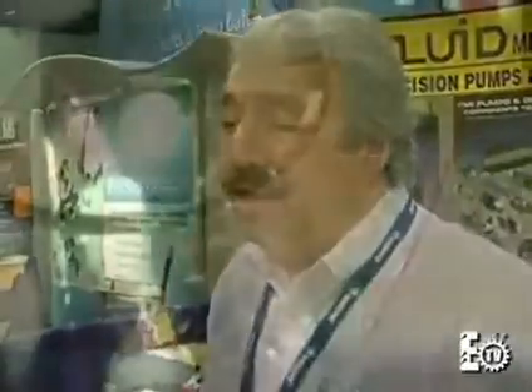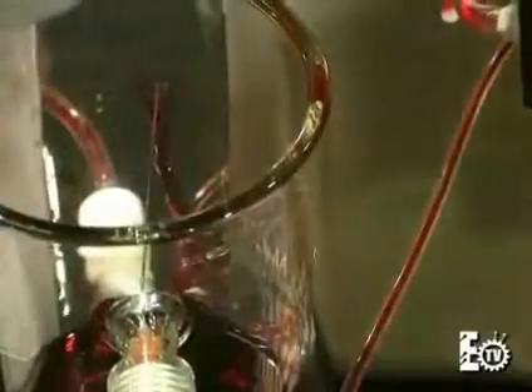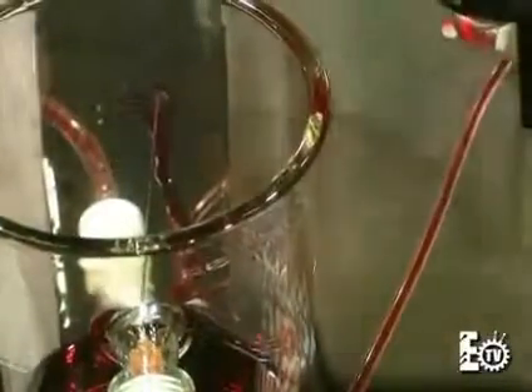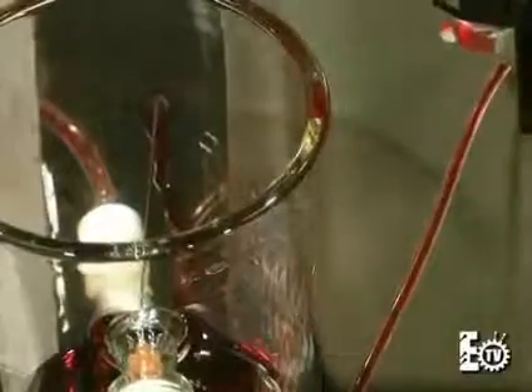What would be the smallest amount of fluid that you could work with in this kind of technology? We could do a half a microliter per stroke, so depending on how many RPMs of the motor you want to deal with. We have different types of drives that we offer, from stepper technology up to continuous motors, RPM motors, and also variable speed type. So a half a microliter times the RPM is going to be my lowest.